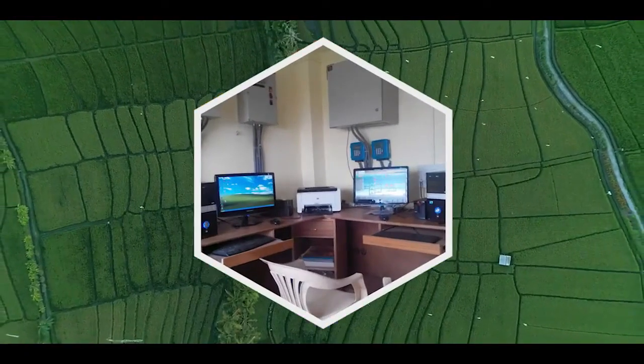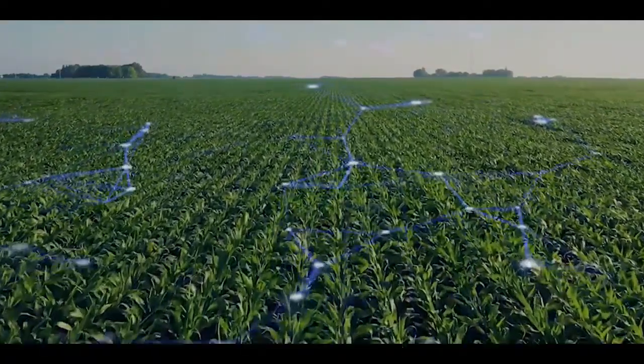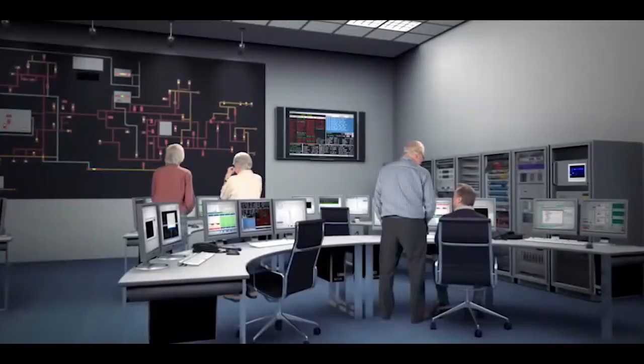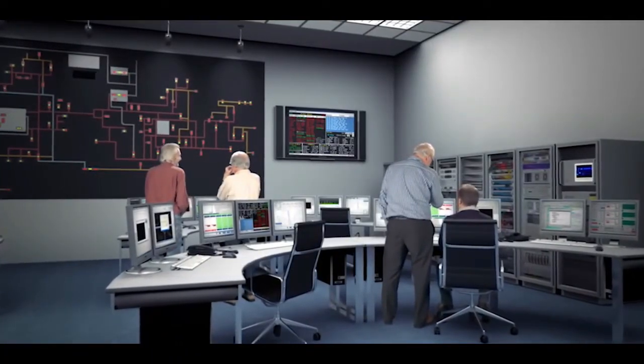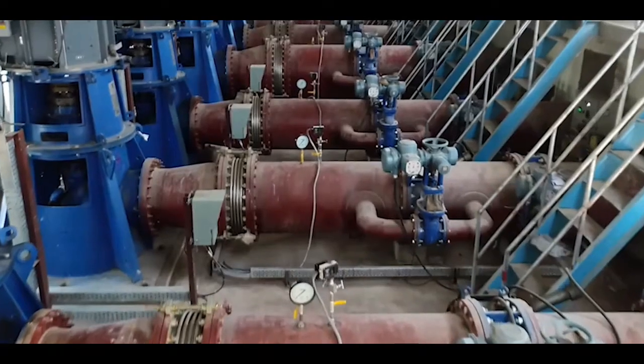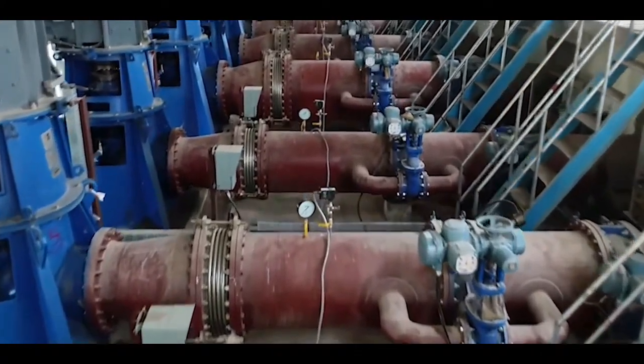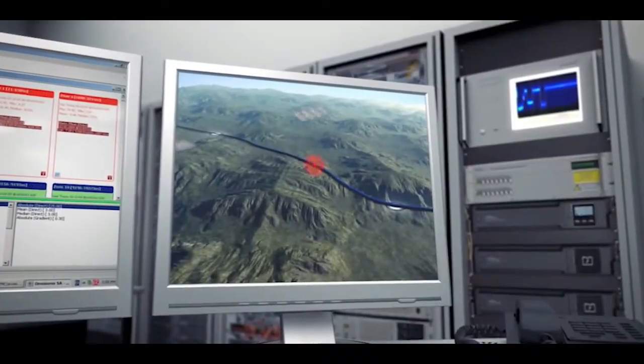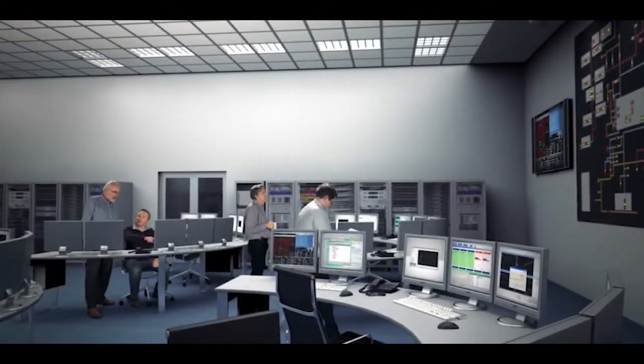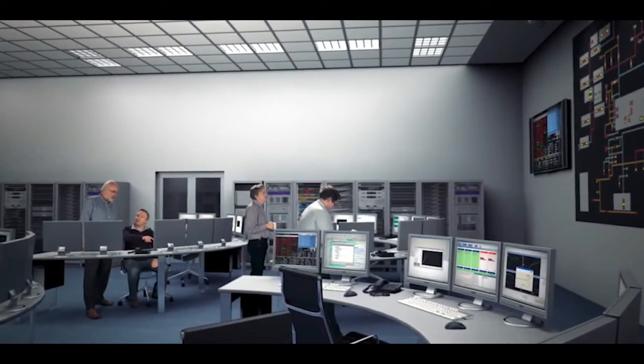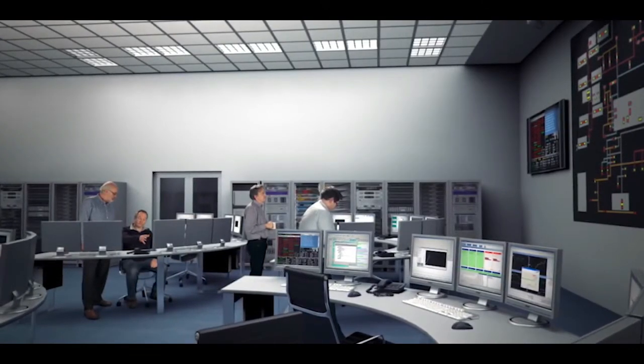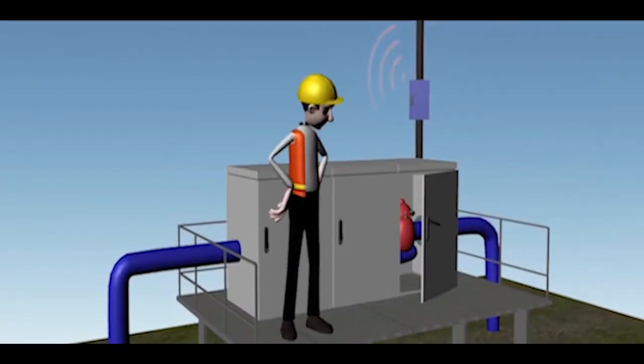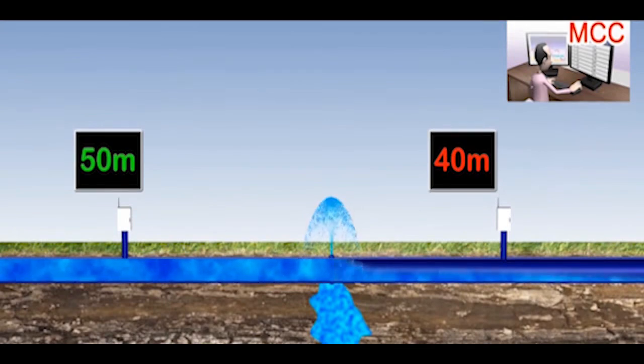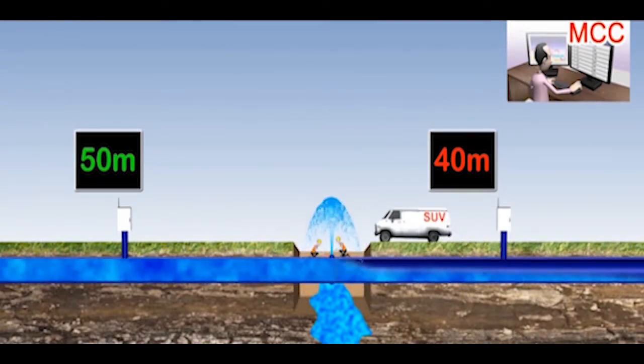Hydraulic SCADA system. Different parts of the line network of the distribution system will be controlled by the SCADA system. This system will get live updates on the registered mobile number. Complete information about the pumps being operated at different pump houses under the scheme will also be available. The entire system can be remote controlled and monitored through a cloud computing system and wireless communication system. An immediate decision may be taken with the help of this system on theft of water, leakages in pipes, and to rectify any malfunction occurring in the whole system.